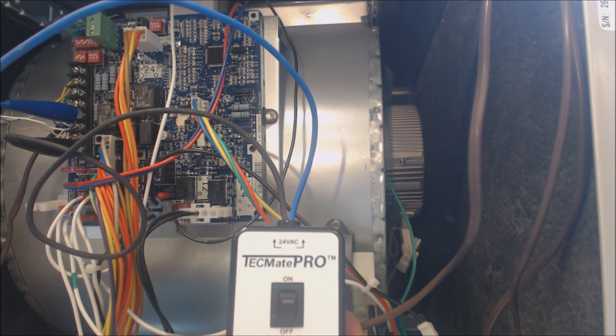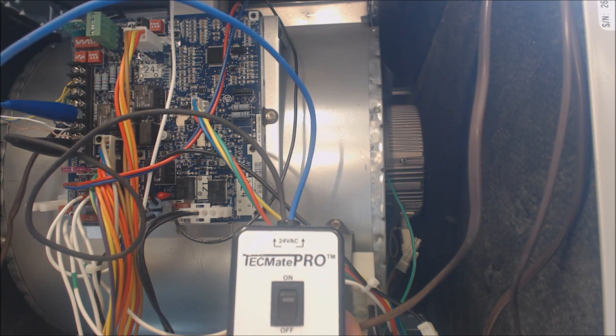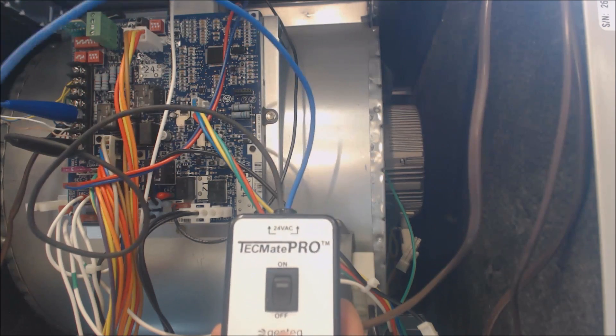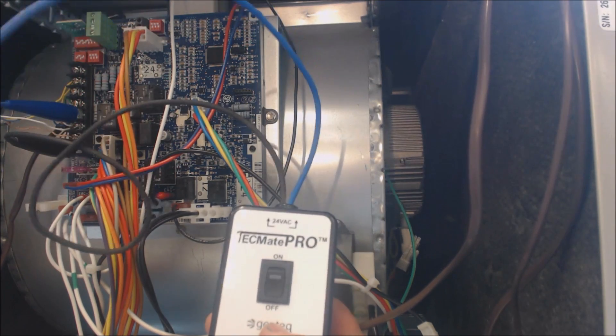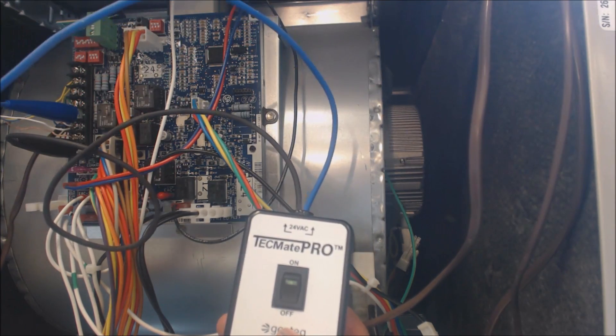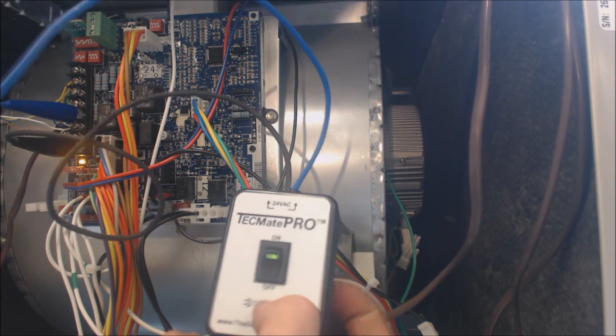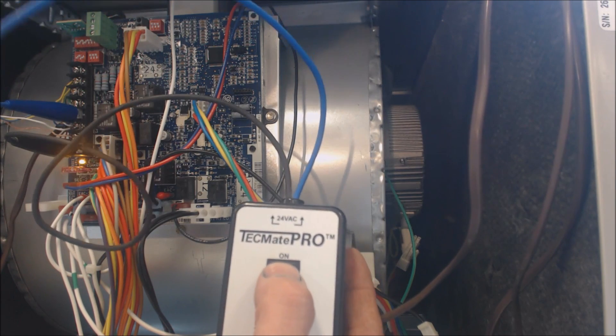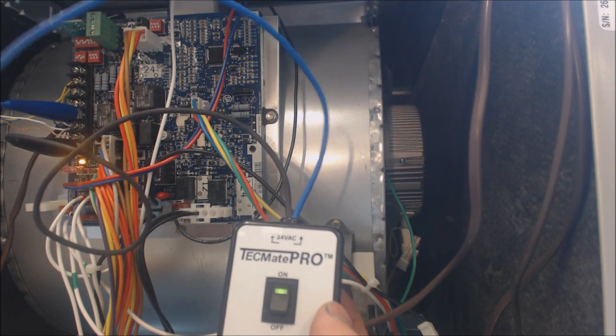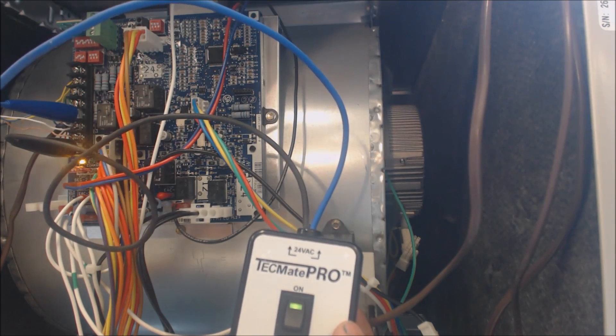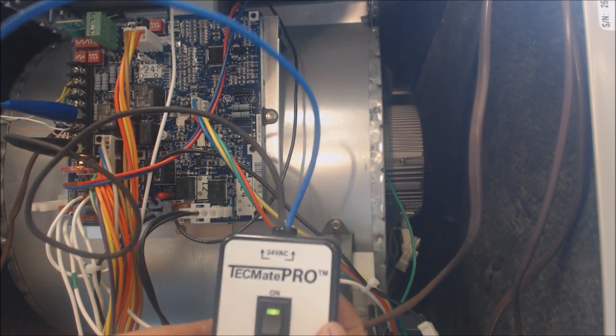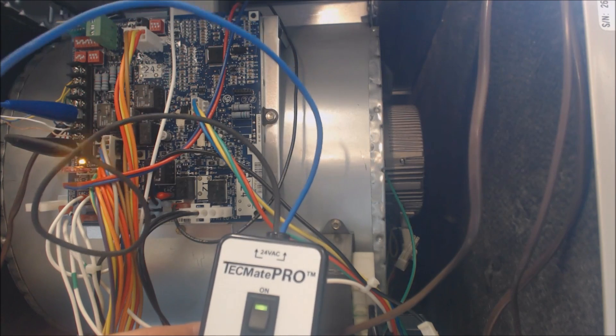Maybe you're in the heat cycle or the cooling cycle, but the blower motor is just not turning on. This is something that you can use to check it out. So we're going to turn the power on now. And if we turn the Techmate Pro to the on position, it's going to give it a signal to go ahead and turn the airflow on.